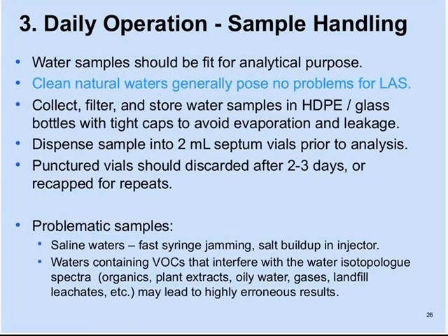There are problematic samples. This has been alluded to or already discussed in the previous talks. Salty waters, why are they a problem? Well, from our experience, they usually result in your syringe jamming up pretty quickly as salt may precipitate or get stuck in the injector, into the needle barrel. And as was mentioned, you would actually get salt buildup in the injector. And these salts, of course, will impact memory and variable results, particularly for 18O.